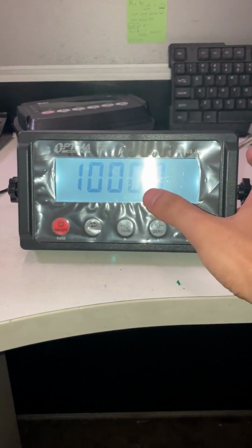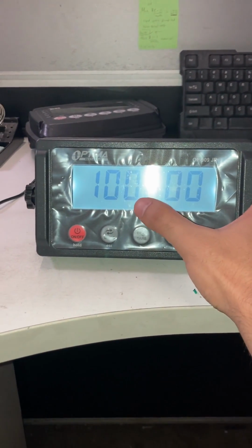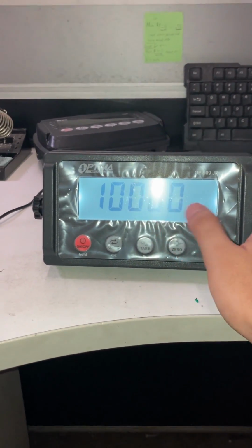C04, you set it to the maximum capacity. So if you have a 5,000 pound scale, set it to 5,000, or for a 10,000 pound scale, make it 10,000. C05, make that 1.